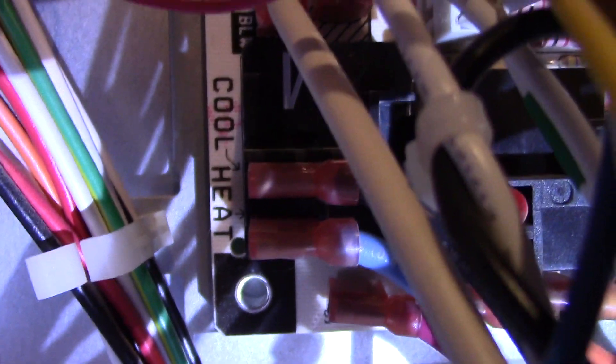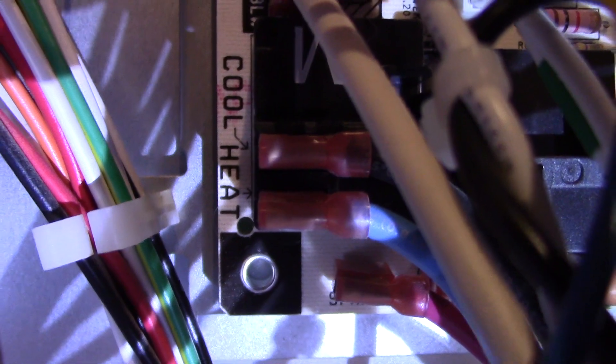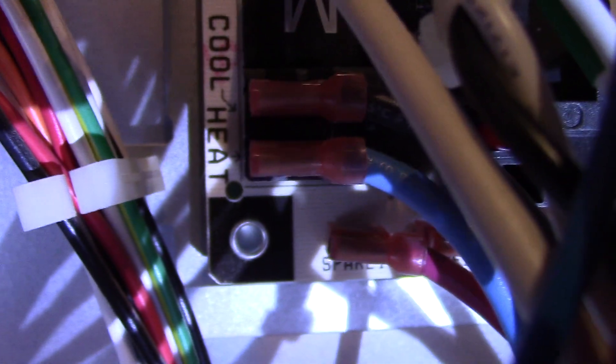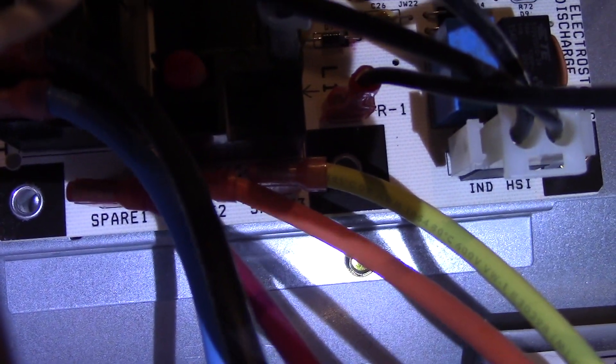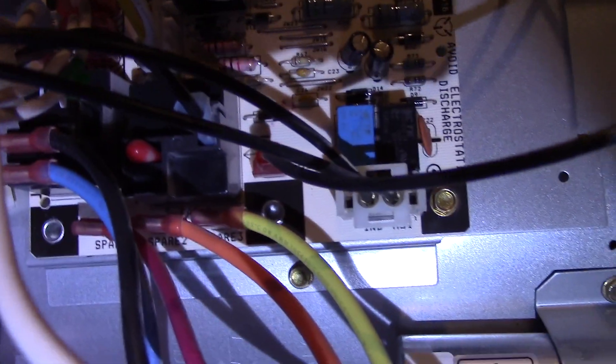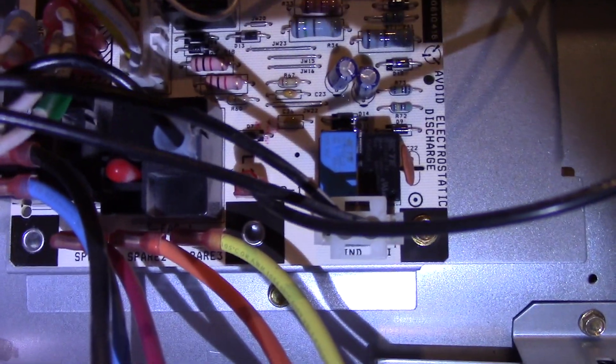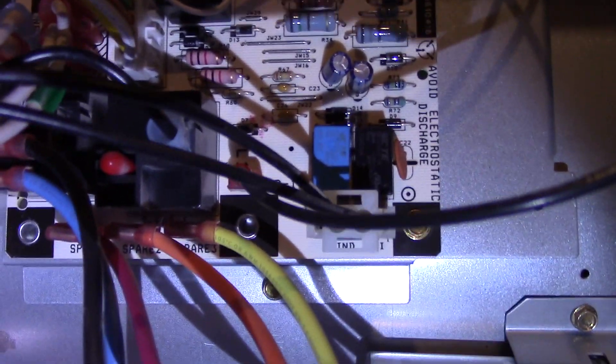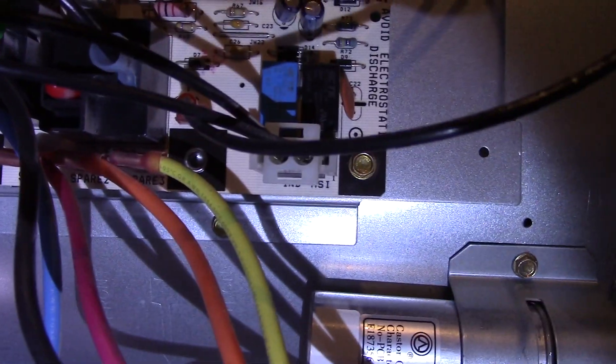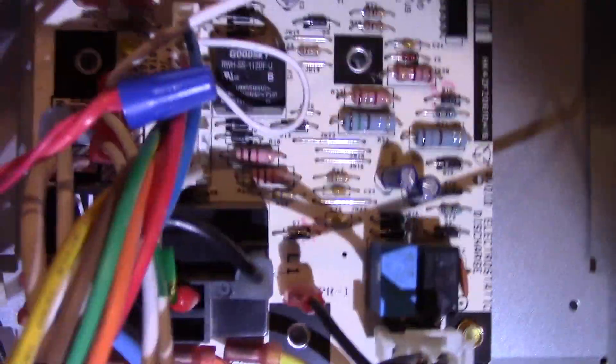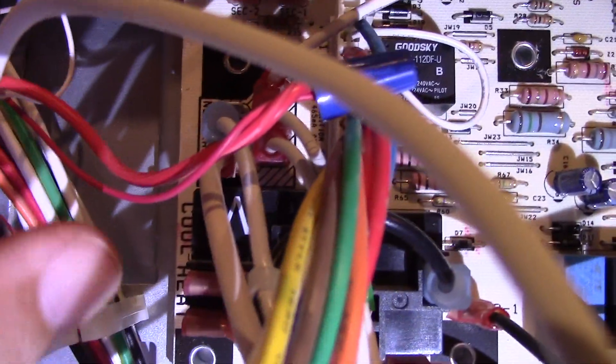I should also state that on this furnace and many other furnaces, if you use fan mode, like how you have on your thermostat, you have the fan auto-on switch. If you move it to on, it's going to use the heat speed as well when you decide to use that option. As you can see right here, cool speed uses high speed and heat uses medium-low. And what's also important to note is down here, you notice how the other wires are connected to spare terminals. Basically, the spare terminal is something that never gets power at all. It's merely there just to keep the unused wires held in place somewhere. They never actually get power.